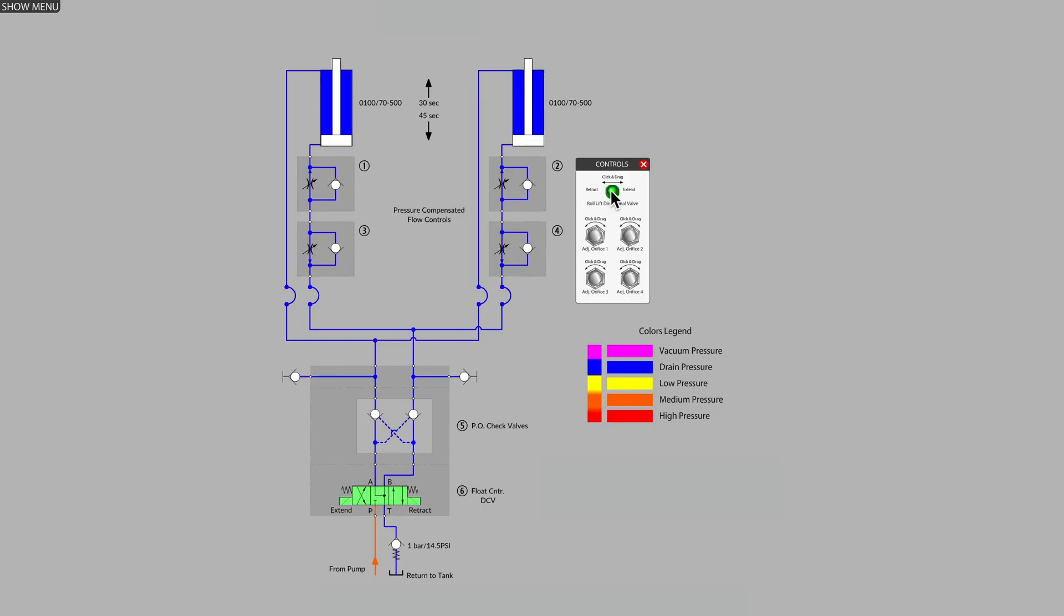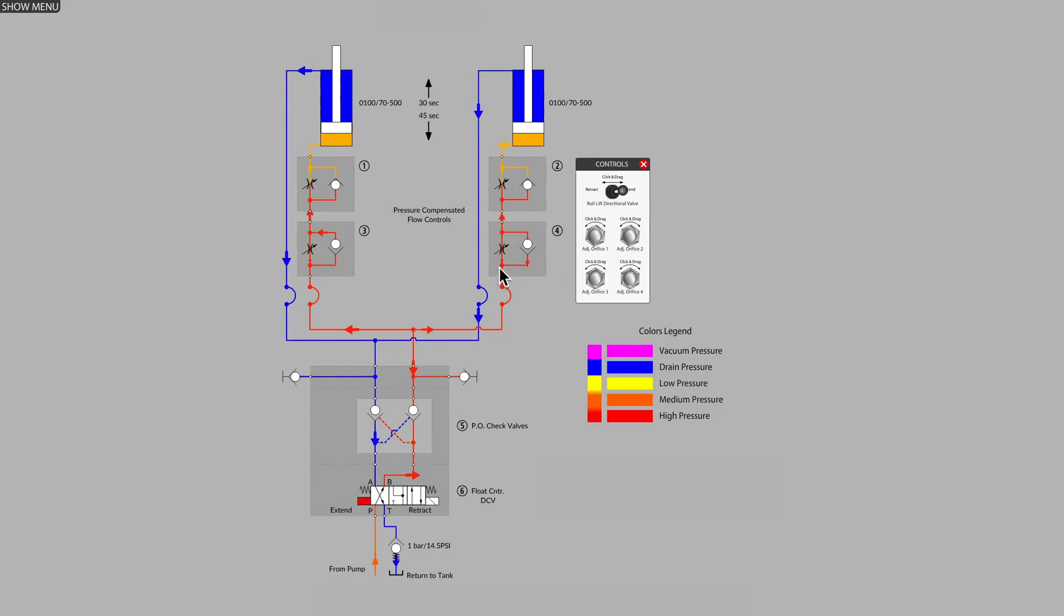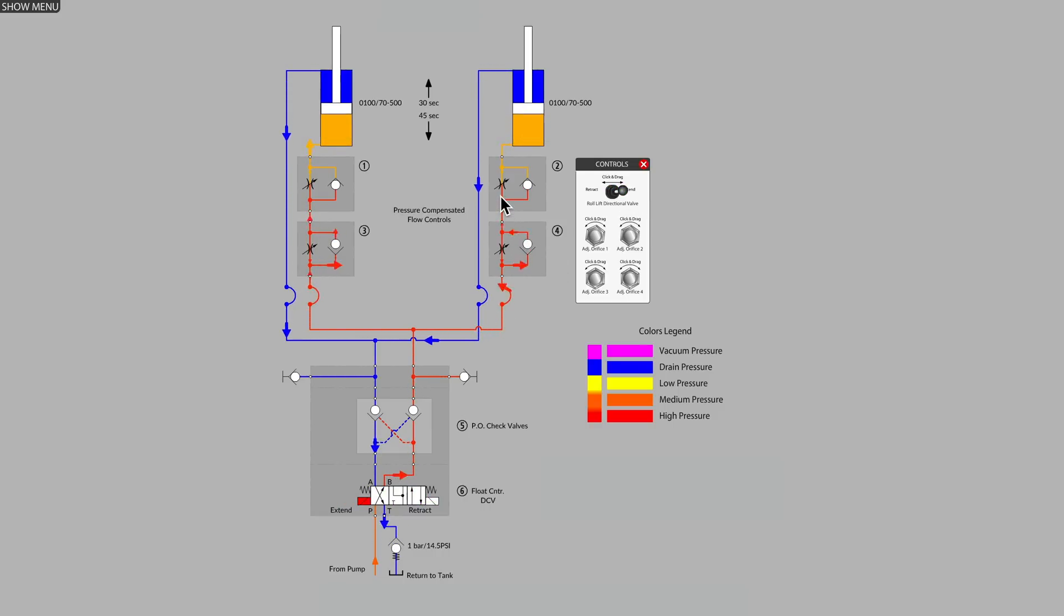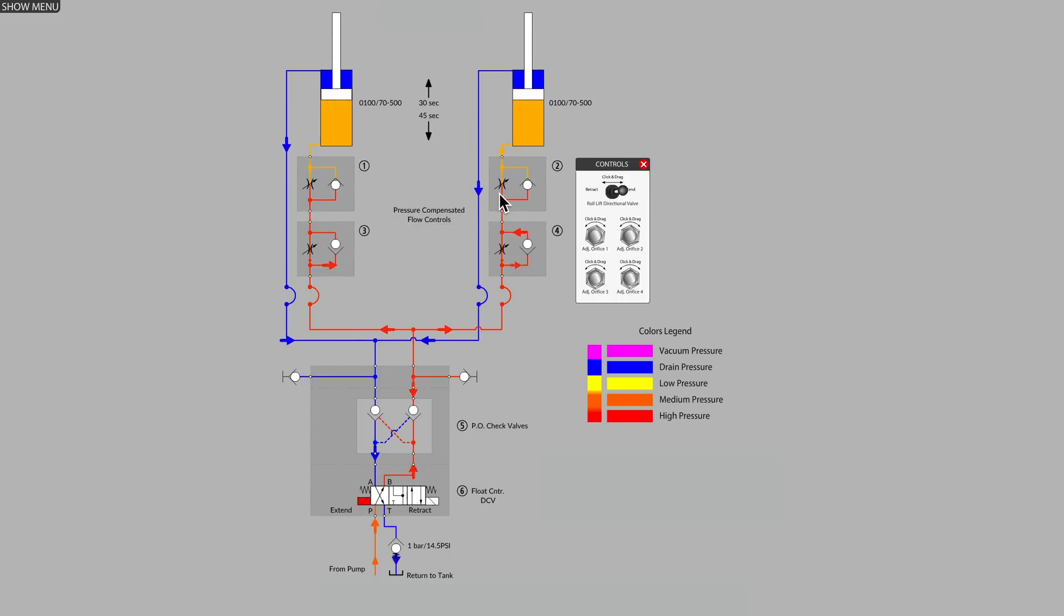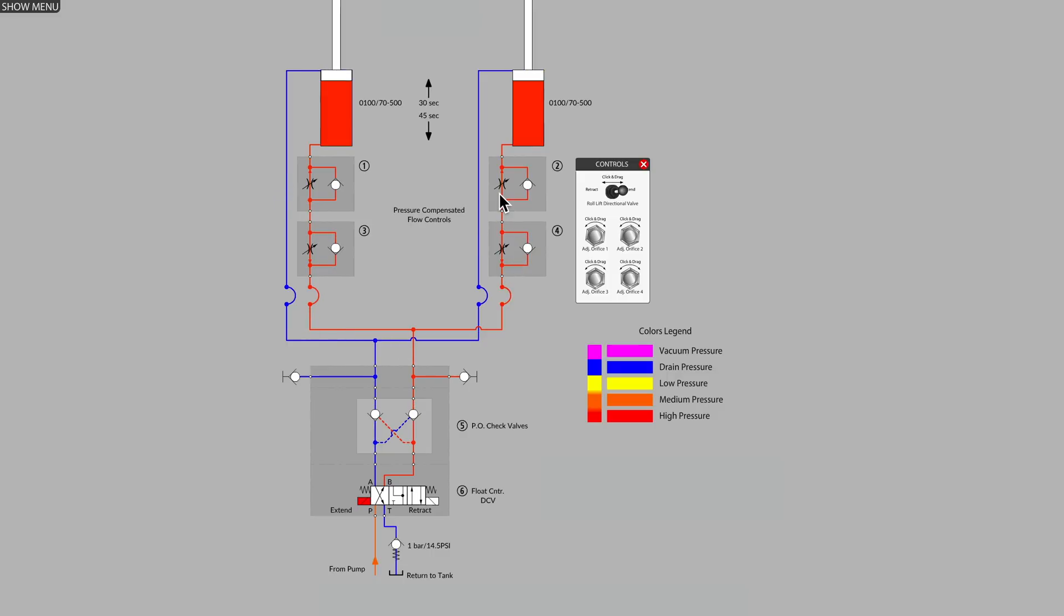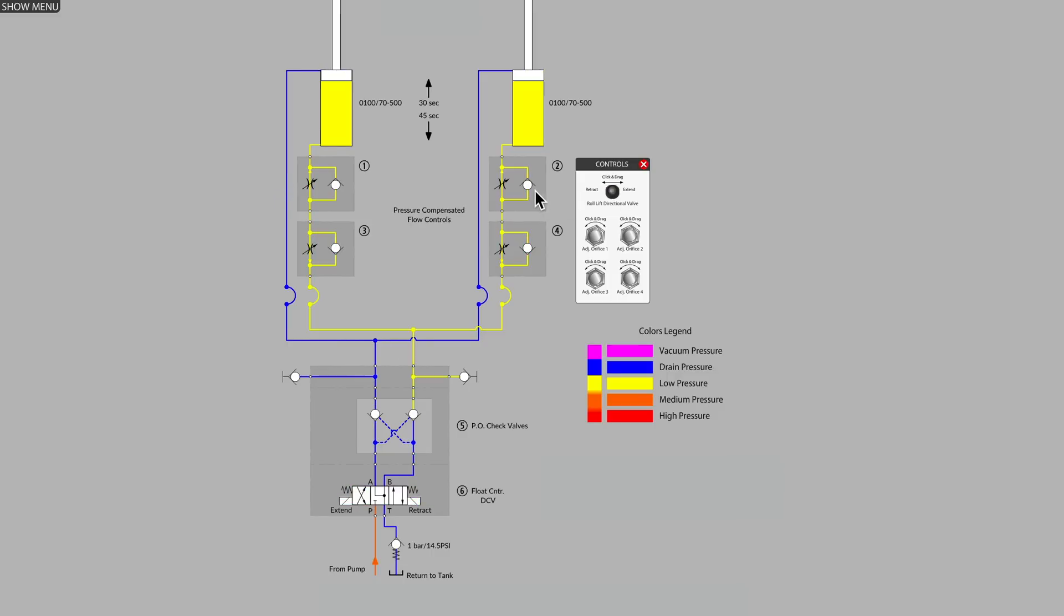When we go into the extend position, oil coming from the B port on the directional valve bypasses the lower flow control and is metered on its way into the cylinder by the upper flow control.